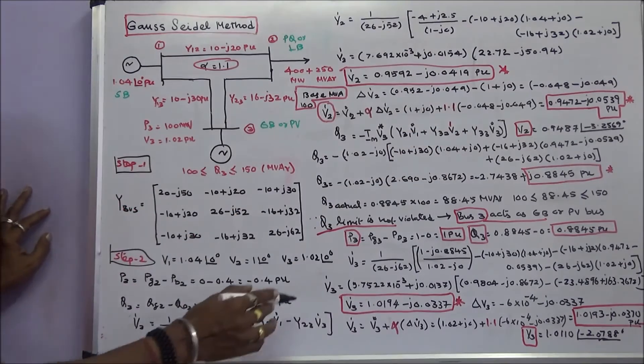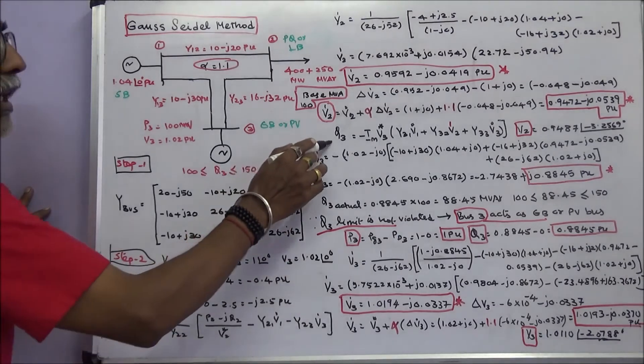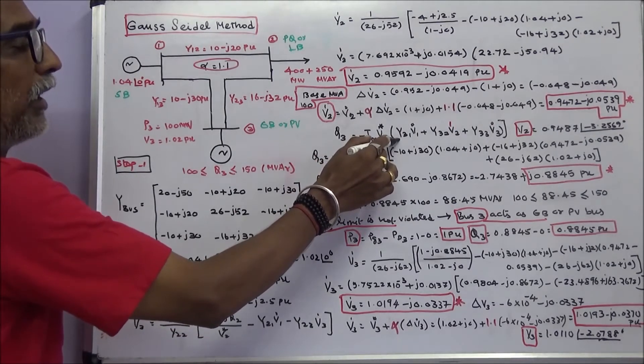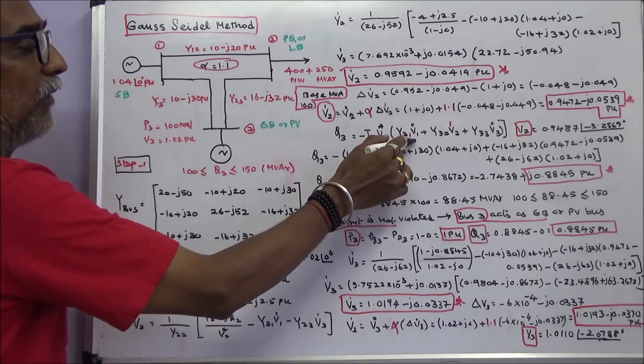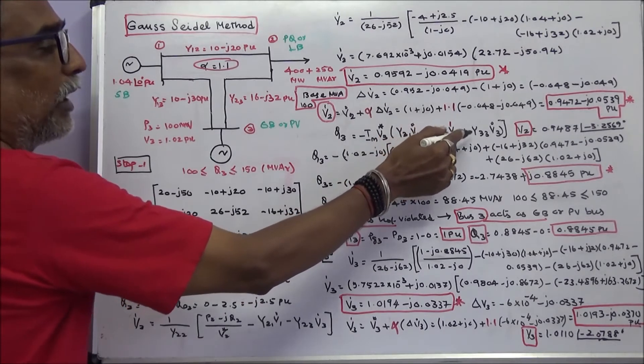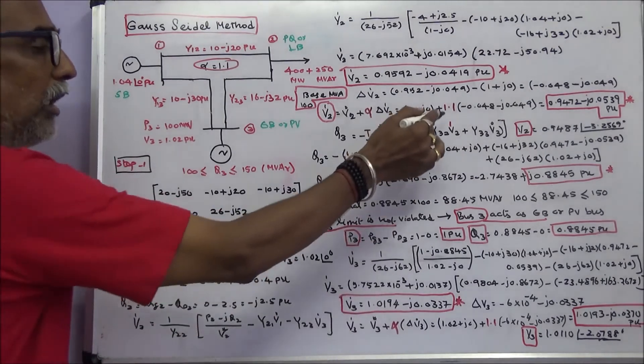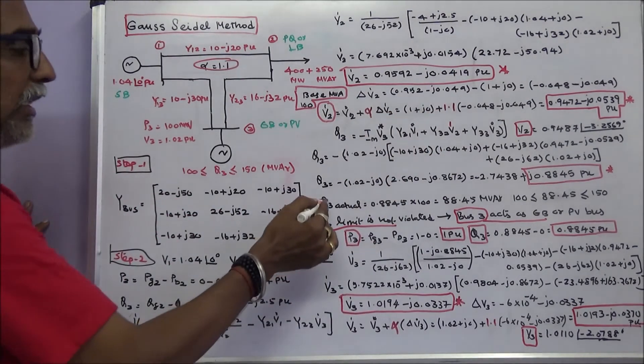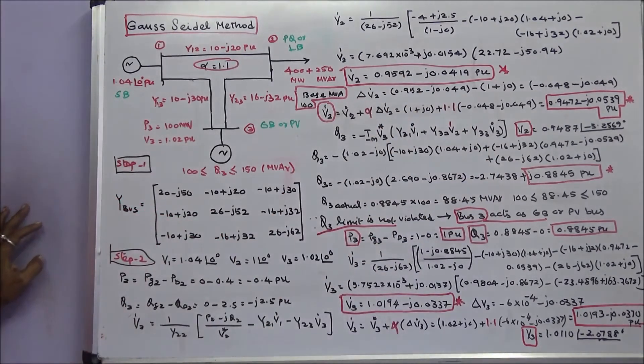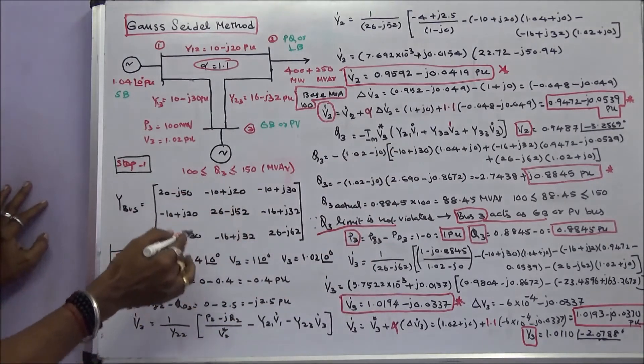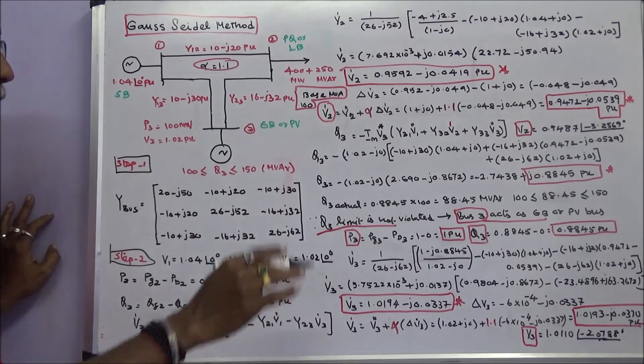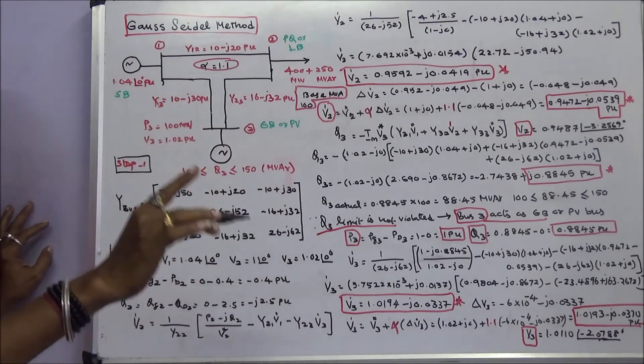Next we calculate V3. To calculate V3, we first need Q3. Q3 is the negative imaginary part of V3* × (Y31·V1_initial + Y32·V2_accelerated + Y33·V3_initial). Substituting all values, Q3 = 0.8845 per unit. The reactive power limit is Q3_min = 1 and Q3_max = 1.5 per unit — the limit is not violated. Hence Bus 3 remains a generator bus or PV bus.